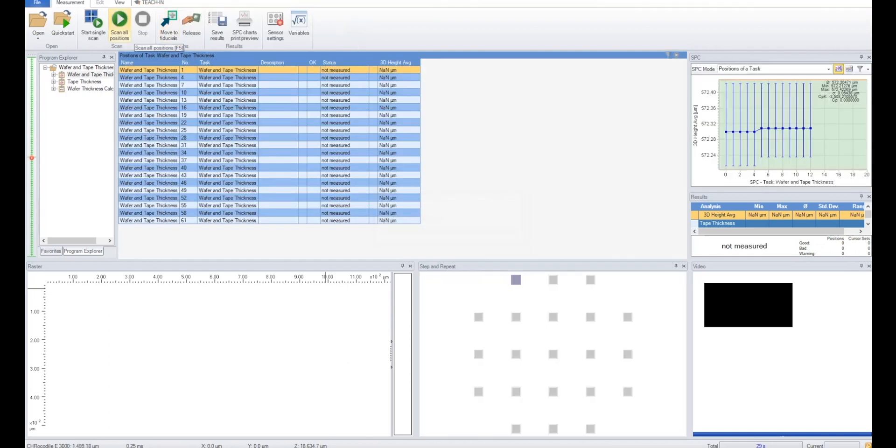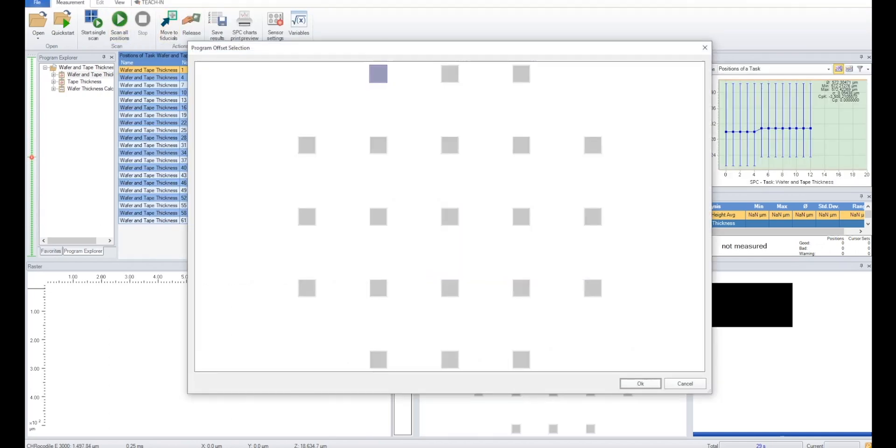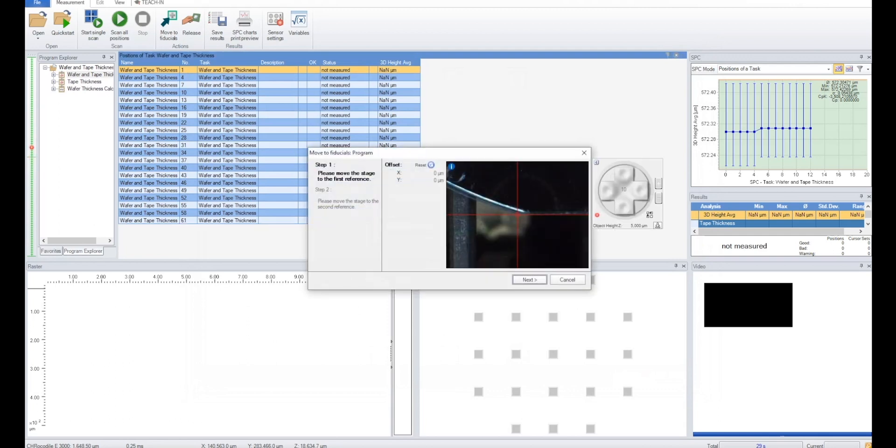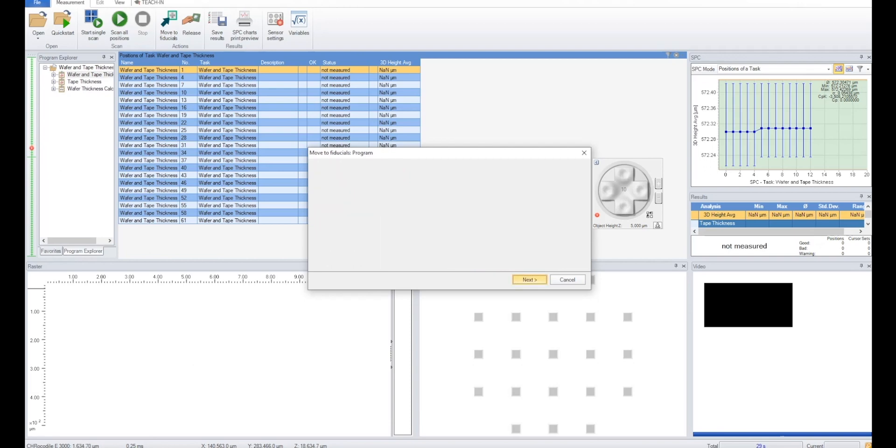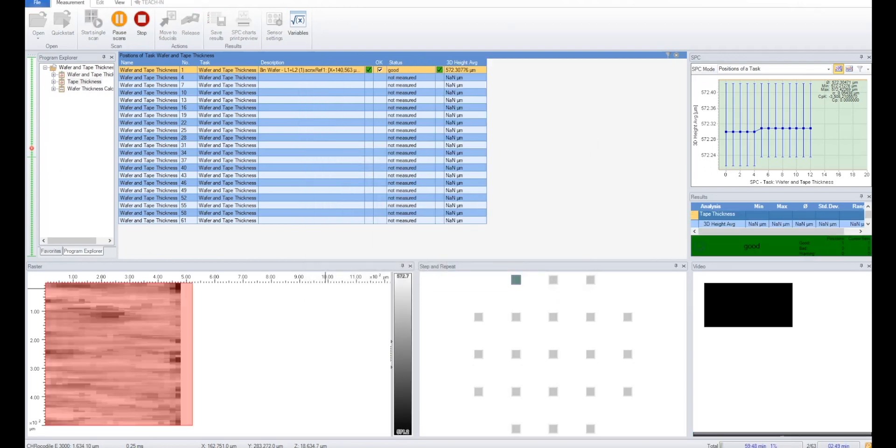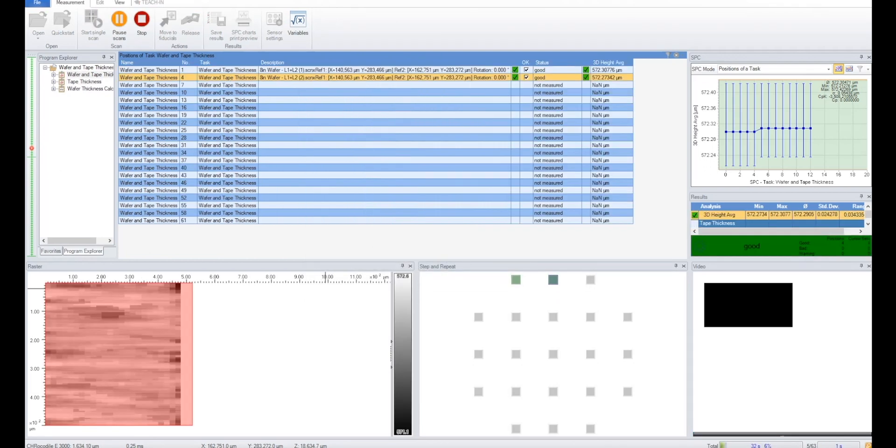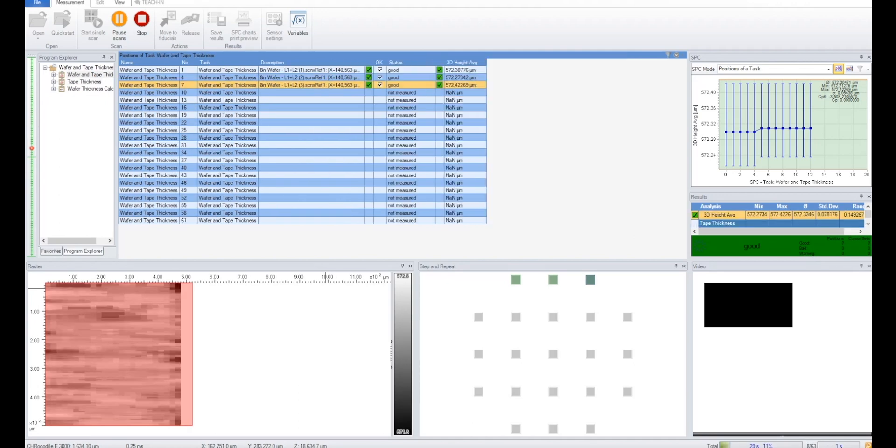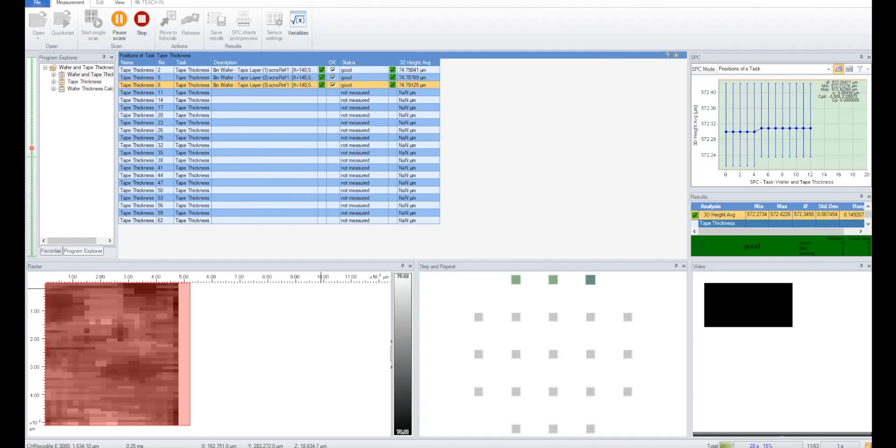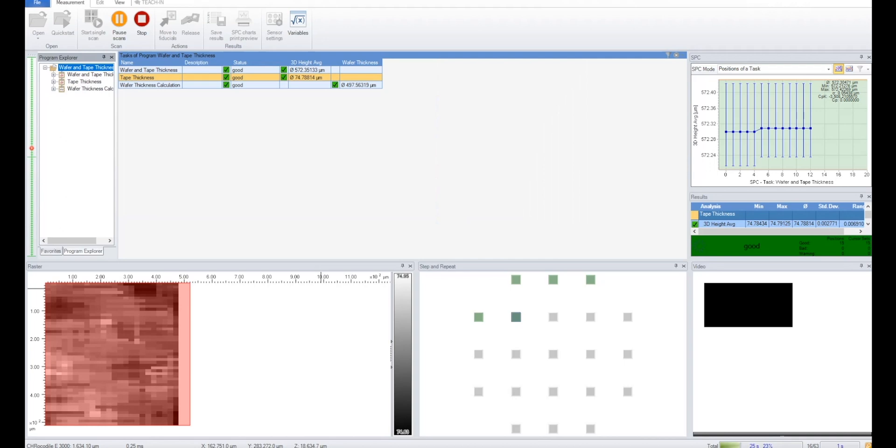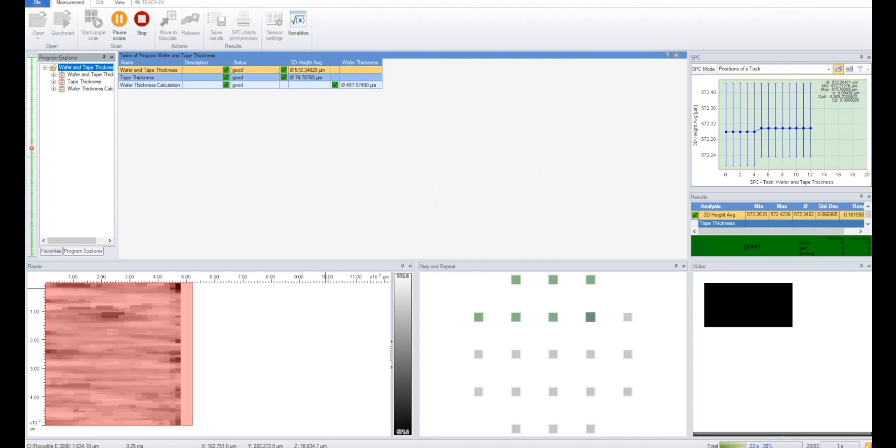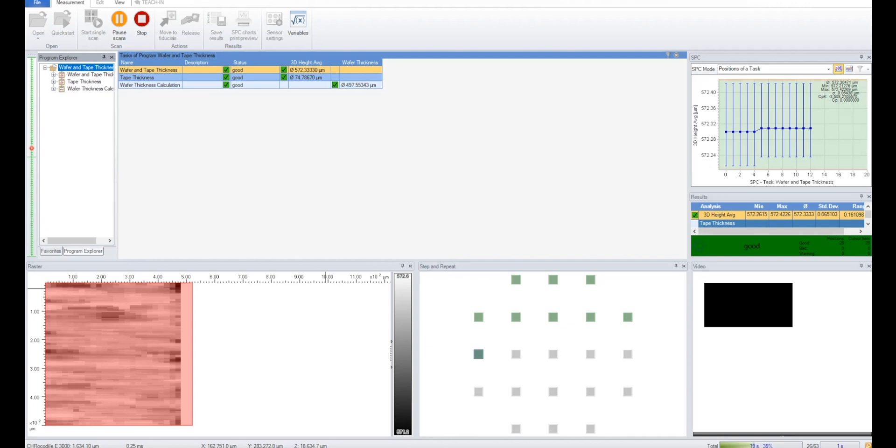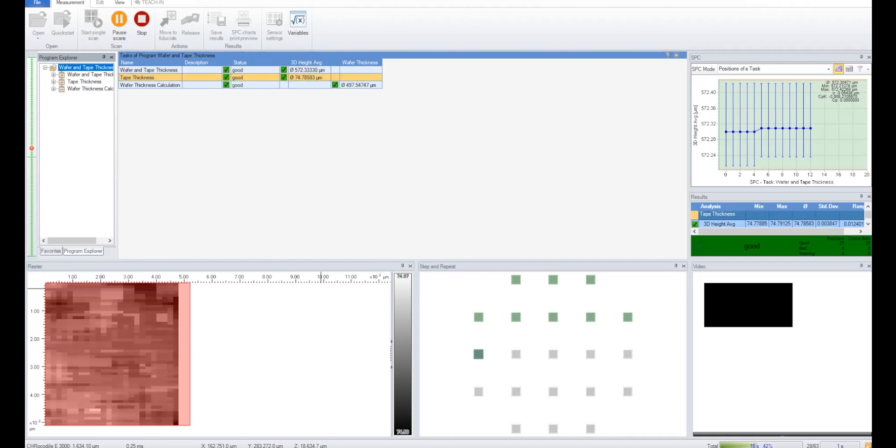When you start the program, you can select which areas of the wafer you want to scan in case you want to do less scans or look at specific areas only. In this case, we will measure every location. Next, the system will perform a fiducial check on the wafer flat in order to align itself. After this, the system will scan each area in sequence. In this demonstration, however, the scans have already been done and the results are simulated using previously scanned data.